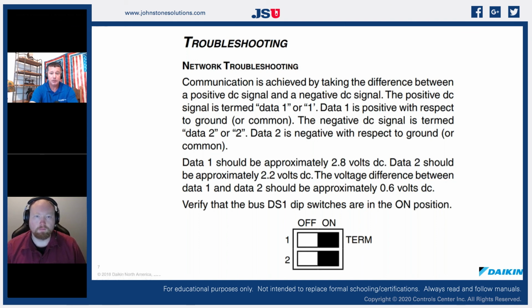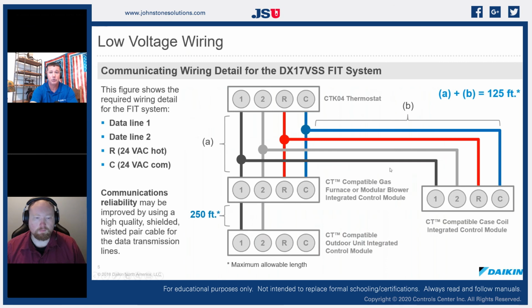And we can check those too. If we look at the actual individual network, I should be able to take my meter and go between 1 and 2 anywhere in this circuit. I should check it everywhere. If I have a problem with my communicating network, say one of my pieces of equipment is not showing up, I need to take my meter and check between 1 and 2 at my coil, 1 and 2 at my thermostat, 1 and 2 at my furnace, and 1 and 2 at my outdoor unit to verify that my entire network is talking properly.